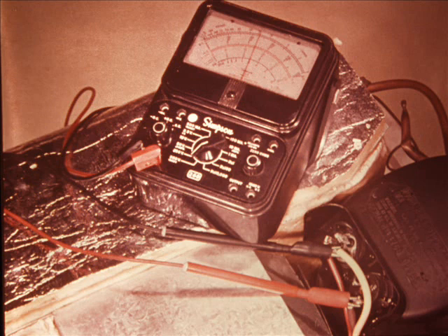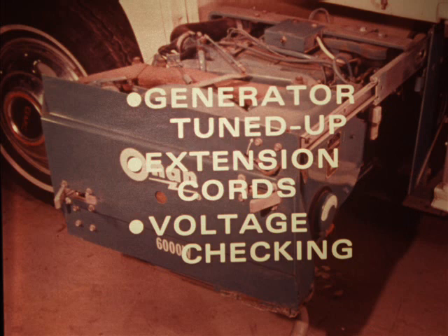Remember, there has to be at least 110 volts at the overload terminal of the compressor and through the overload to the compressor O terminal. If there isn't, troubleshoot the electrical system as described in the maintenance manual. Then, where low voltage has caused the problem, explain to the customer about keeping the motor generator properly tuned up, about voltage losses in extension cords that are too long or not heavy enough, and about checking for voltage before turning on the air conditioning.